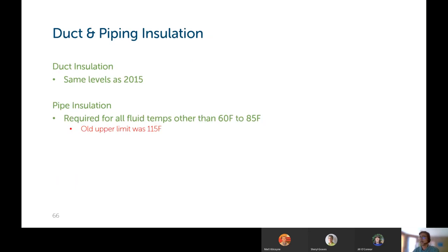Duct and piping insulation. Duct insulation levels are all the same as the 2015 commercial code. Pipe insulation is all the same, but is now required for all pipe fluid temperatures outside of 60 degrees Fahrenheit and 85 degrees Fahrenheit. The old upper limit was 115 degrees Fahrenheit, so that has been brought down, and insulation is required for cooler hot water temps.